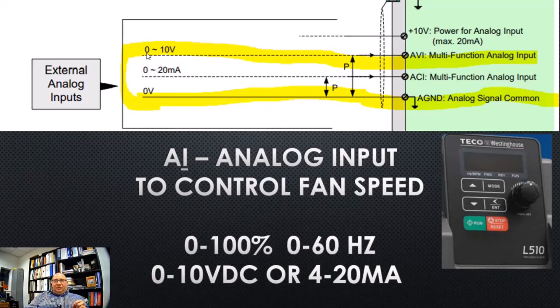So here's a 0 to 10 volts DC. It is polarity sensitive, so this would be the positive, and this would be the negative. And when we go to the bench and do it in the shop, we're actually going to give you a 9-volt battery. Now you may not get the full 100% output, but at least you'll get 90% out of a 9-volt signal versus 10 volts. You could also use a signal generator.